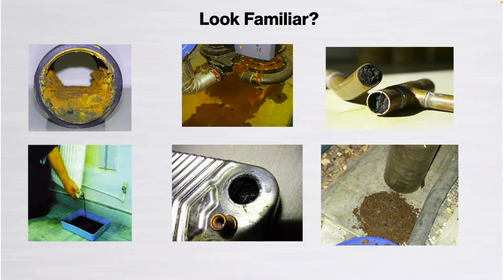Pump seal failure in the middle. Generally, the quickest giveaway is a pump seal failure. The words I've heard from many sales engineers and certainly contractors in the US is, they say it's bad pump seals. Generally, pump manufacturers do not make bad pump seals. As you can see from that photograph there, they're simply not designed for such poor water quality. Otherwise, they'll be used for effluent pumps or such. Of course, then on the right-hand side, we have blockages. And once we get to a blockage in our system, huge costs then come into getting to that pipework and stripping it out to change it.